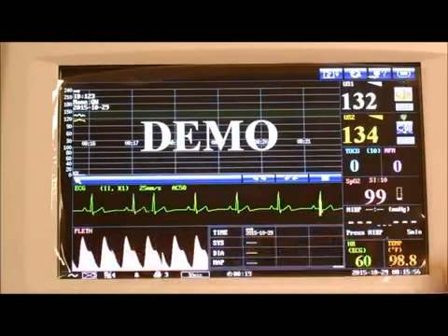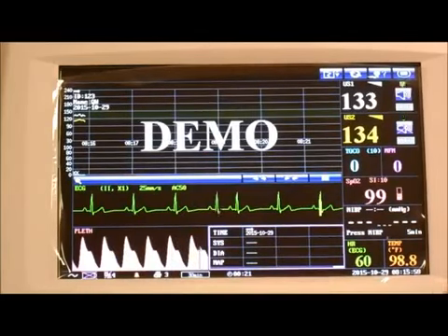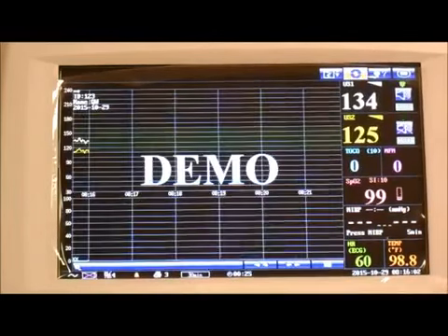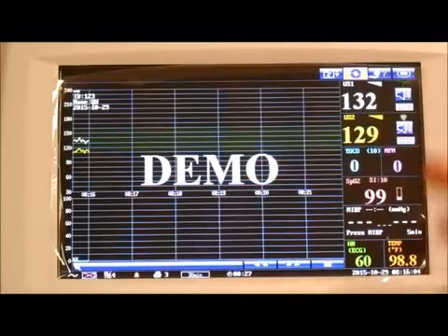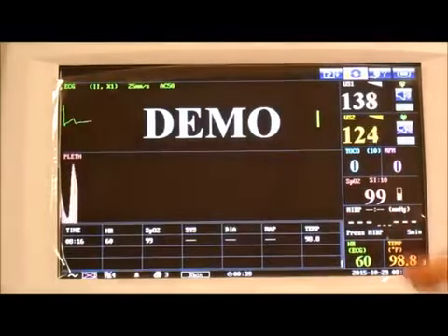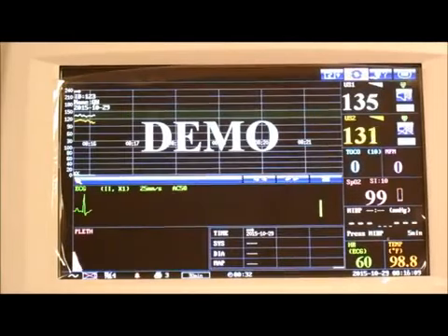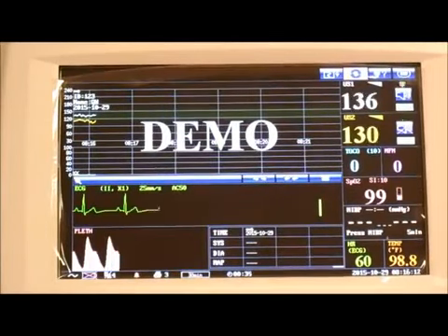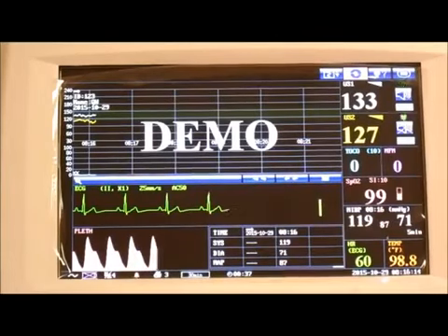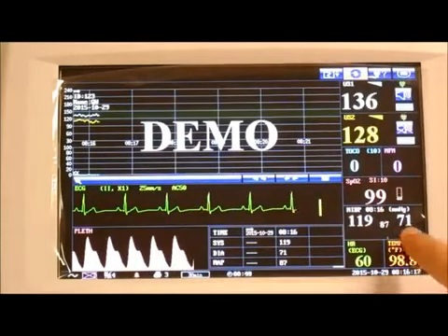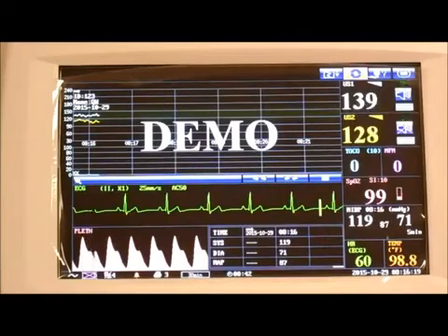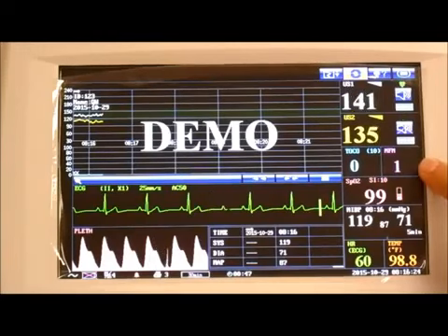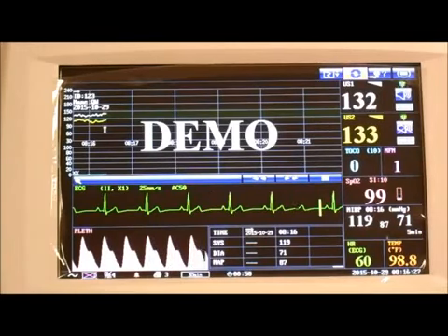So here we have the fetal parameters and the maternal parameters. Again, we can toggle between different screen views. Now we're in the fetal parameters only, maternal parameters only, and a combination of both. We press the NIBP key to take a reading, and now it'll take another one automatically in 5 minutes because that's what we said. If the patient presses a remote marker, there's going to be an indicator on the screen, the MFM, to serve as reference. So it's that simple. You place all the transducers on your patient.